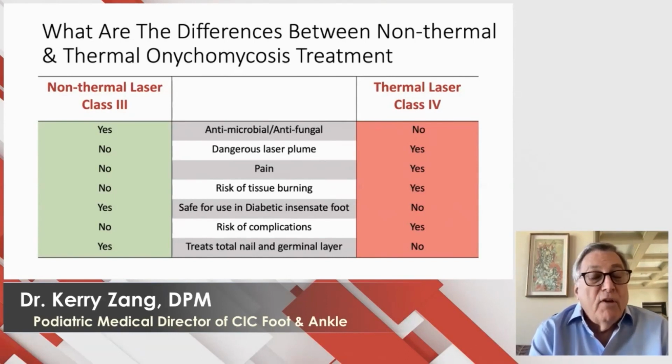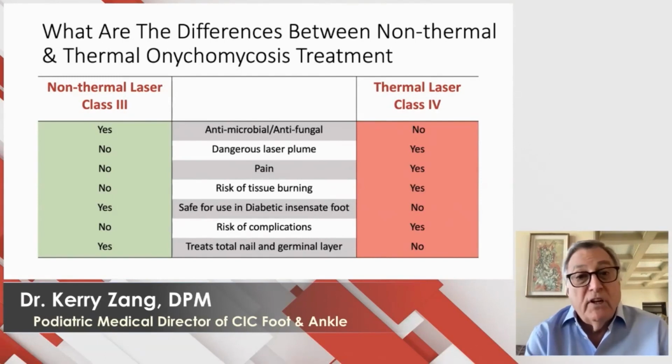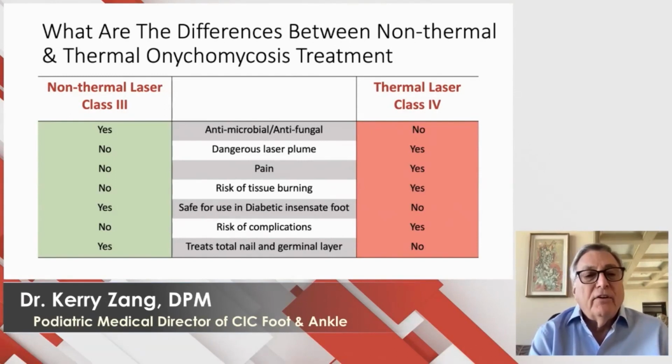If any of you have been around or in the room when they've utilized the class 4 laser, you can smell a little bit of the laser plume. Sometimes you can even see it. Laser plume is not present with the non-thermal lasers. It definitely is present with thermal hot lasers.